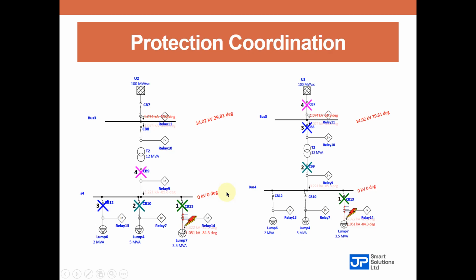Now, there's a very small difference between protection coordination and fault isolation. In an ideal case, we are not expecting our relay to fail. We are expecting that a fault here should be isolated by this relay and circuit breaker 13, as seen in both cases.